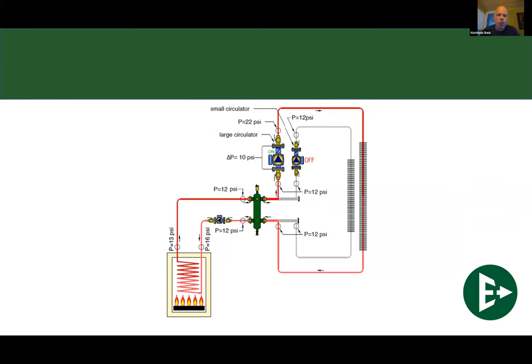Question I get on this one is in regards to where do I put the expansion tank on an air sep? Usually I want that on the boiler return side before the pump going back into the boiler. Make sure that I'm pumping away from the expansion tank. It's still a part of low pressure. Doesn't matter where it goes in, but a good place to put it is right there.